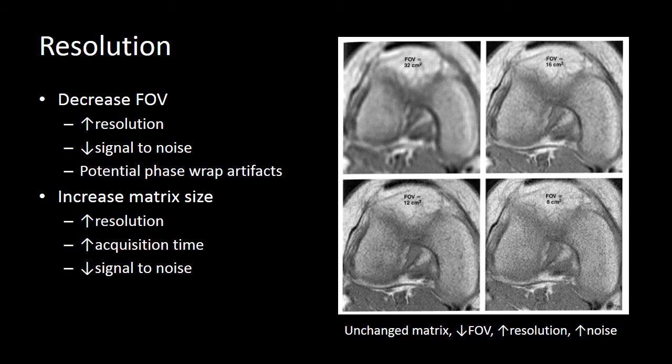Let's look at an example. Here we have four different images of the knee. We have cropped some of the image. You can see field of view 32 centimeters, 16, 8 centimeters, and 12 centimeters. In each case we're not changing the matrix, but we're decreasing the field of view over time. By decreasing the field of view from 32 to 16 to 12 to 8, we get progressively better resolution.